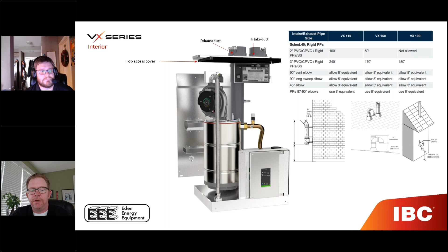Then we have the Sim Plus. This is a really nicely designed product by IBC - one piece that was made by IBC and has been proven in the SL equipment. It provides your ignition, flame proving, and flame safety monitoring, and it also has direct control of the combustion fan and the gas valve. When you look in this unit and see so few parts, that's because IBC has invested so much time into engineering two parts of this unit: the Sim Plus and the V10 control we talked about before.